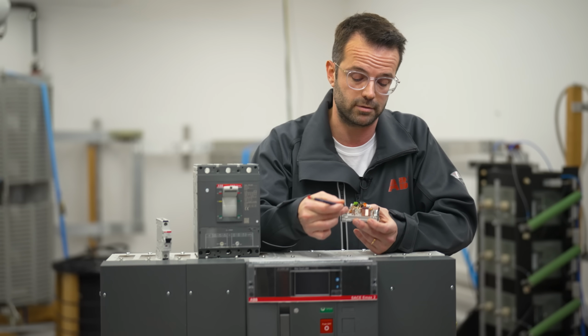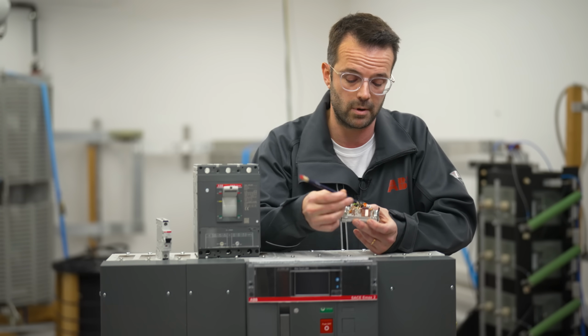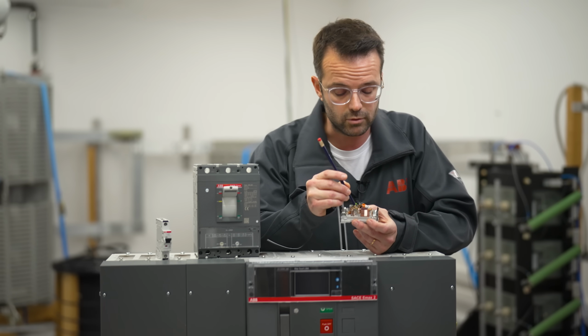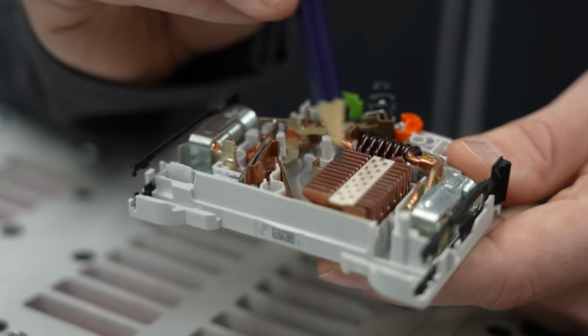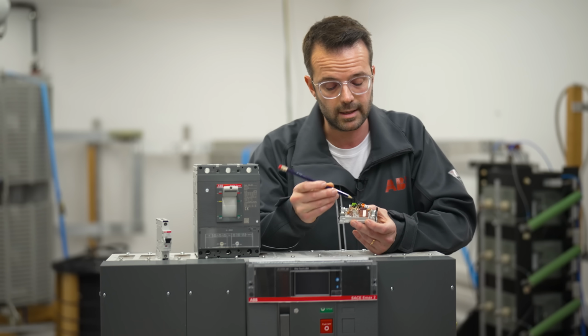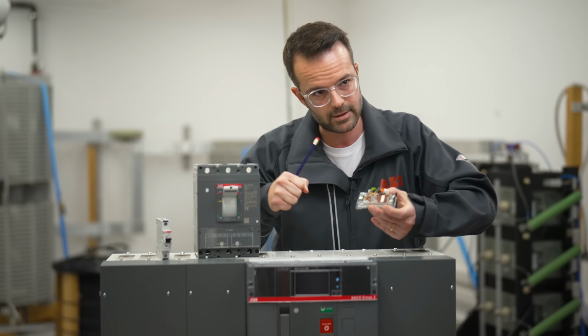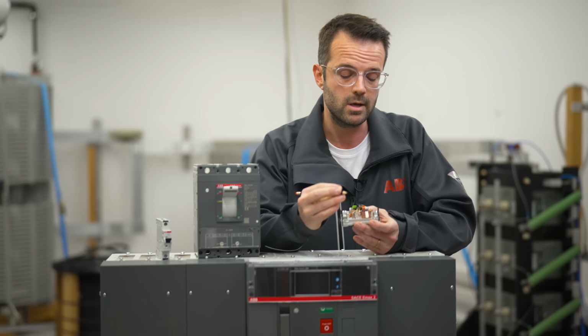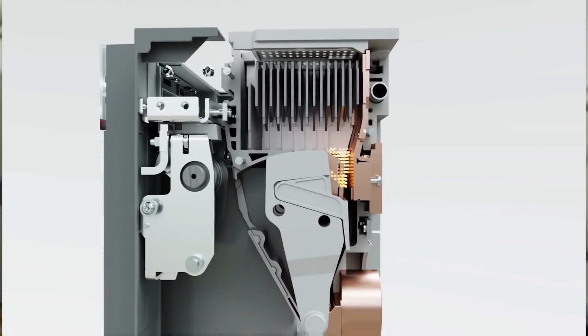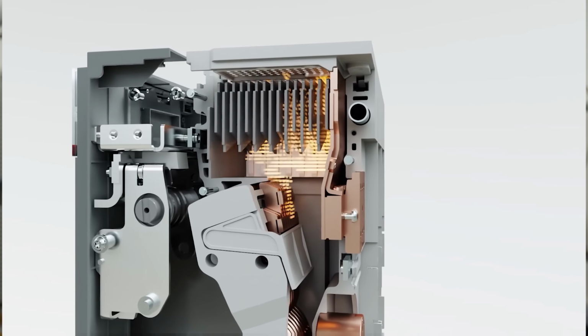The tricky part is that as soon as the contacts open, an electric arc forms. It's a self-sustained bridge of plasma which keeps the current flowing between the two contacts. The structure of the circuit breaker, as you can see here, this is the arc chamber, is meant to take this arc and drive it down the arc chamber, in what we call the arc chute, so that the arc is stretched, elongated, and cooled down, so that these splitter plates can stop, interrupt, and extinguish the arc.